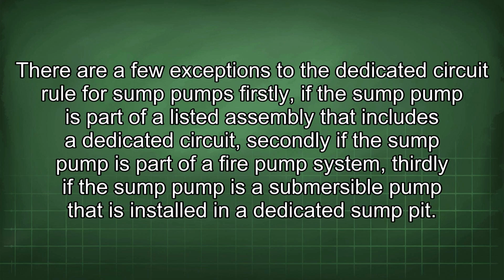There are a few exceptions to the dedicated circuit rule for sump pumps. Firstly, if the sump pump is part of a listed assembly that includes a dedicated circuit. Secondly, if the sump pump is part of a fire pump system. Thirdly, if the sump pump is a submersible pump that is installed in a dedicated sump pit.